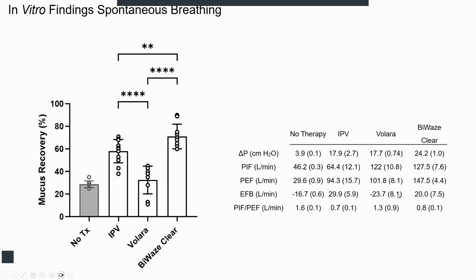And overall, we showed that the IPV device and the BiWaze Clear definitely have this expiratory flow bias, so they're producing these micro coughs, whereas the Volara device favors inspiratory flow and has a fairly low expiratory flow in this case. Another thing that's interesting is that with each of these devices, you increase the peak inspiratory flow beyond what they're breathing, right? And some of them are higher than others. We'll speak about that a little bit later.